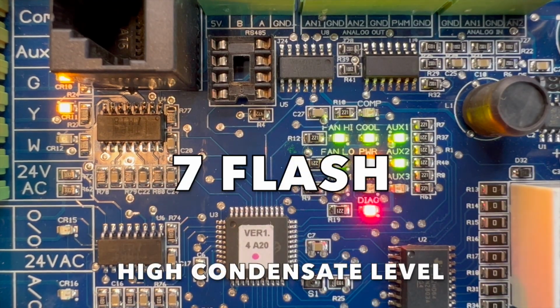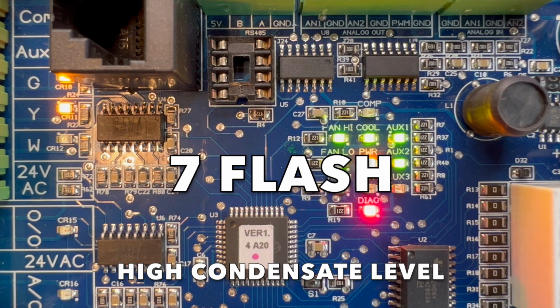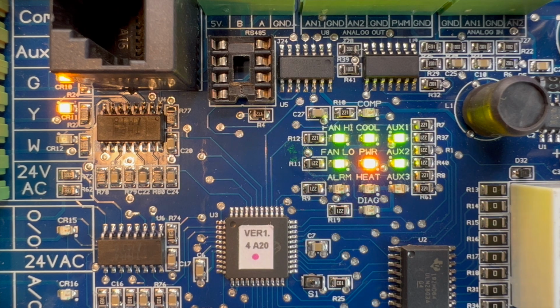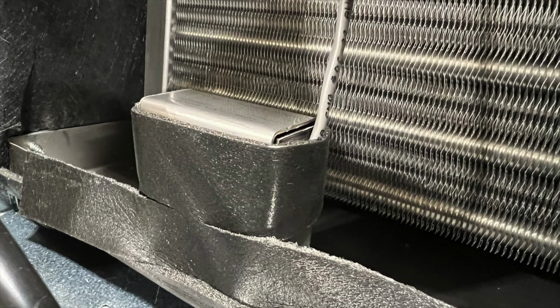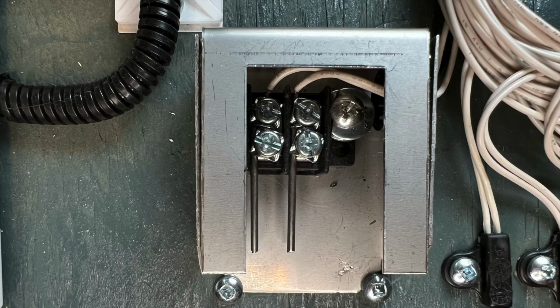Seven flash, high condensate water level in the evaporator drain pan. Make sure the condensate level sensor is at the correct height and it is insulated with Armaflex. Check drain pan slope and make sure the condensate drain is installed correctly and it is free flowing. Here's what the condensate sensor looks like with the Armaflex removed.